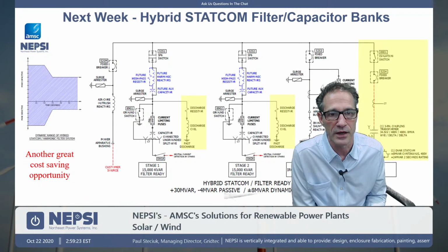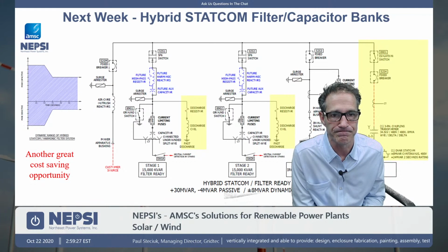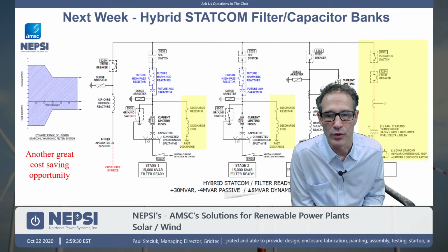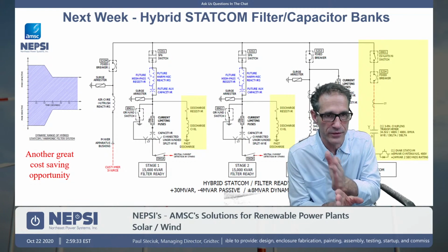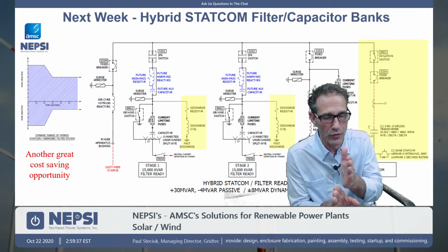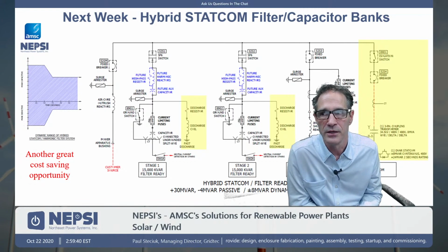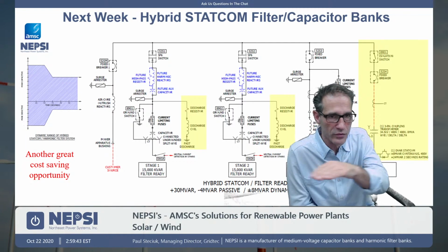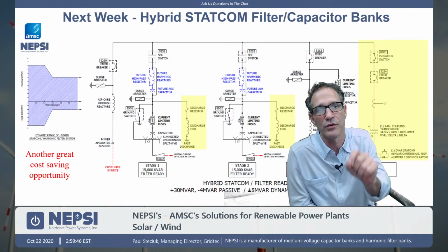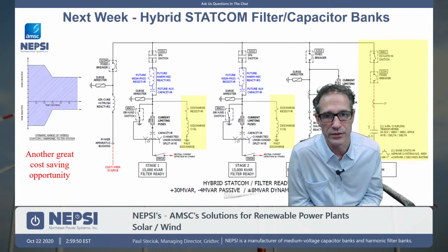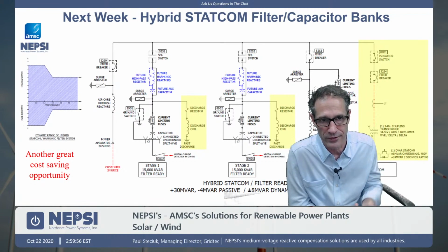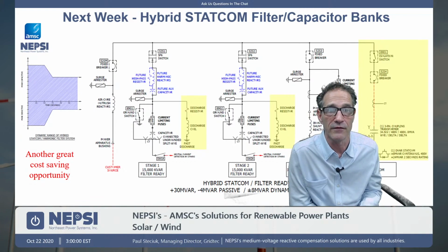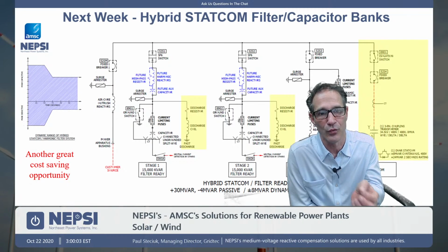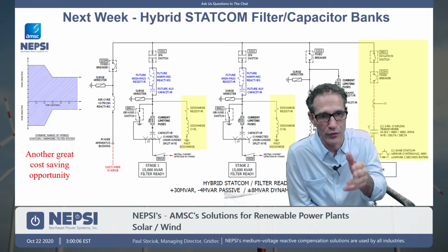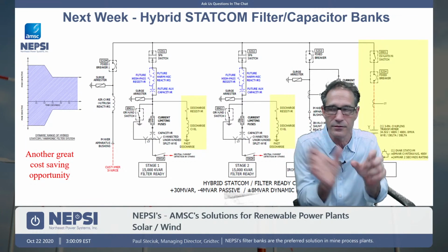It's very tricky when you have a high frequency resonance, because when you tune to the 40th harmonic, you get a resonance beneath the tuning point. And that resonance is going to move around based upon the short circuit impedance of the network. So putting a resistor around the reactor will help to flatten that resonance out, but that resistor value would have to be relatively low. Okay, low in value, which means low damping factor. So low resistance, low damping factor, and you'll get rid of that resonance. That would be my first attempt. But you have to make sure you do not magnify the other harmonics where you get the increased impedance because of resonance with that filter bank against the source impedance.